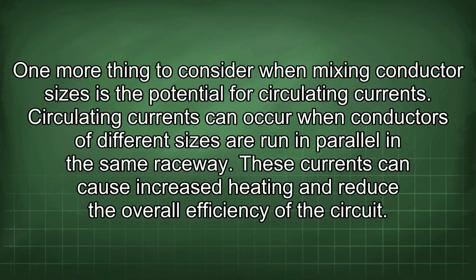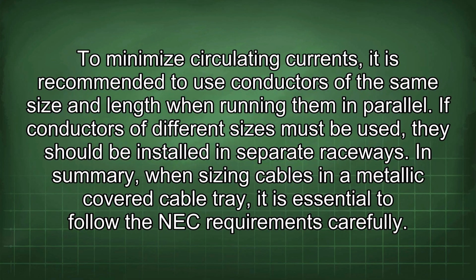One more thing to consider when mixing conductor sizes is the potential for circulating currents. Circulating currents can occur when conductors of different sizes are run in parallel in the same raceway. These currents can cause increased heating and reduce the overall efficiency of the circuit. To minimize circulating currents, it is recommended to use conductors of the same size and length when running them in parallel. If conductors of different sizes must be used, they should be installed in separate raceways.